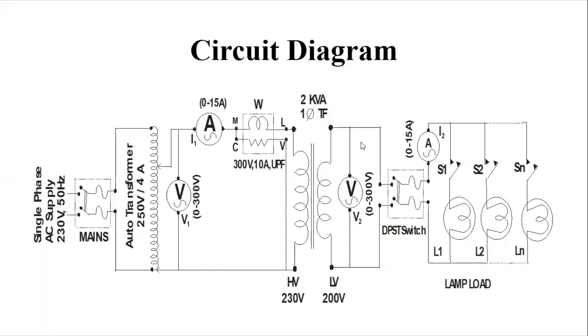Next, look into the secondary side connection. From the secondary, that is from the 0 terminal, the connection has to be given to the DPST switch. From the 200 volt terminal, the connection has to be given to the DPST switch. In the secondary side, we can find different tappings on the transformer. Since the maximum voltage is 0 to 230 volts, in order to get 200 volts, we need to give the connection to the 86.6% tapping. From that tapping, the connection has to be taken out.